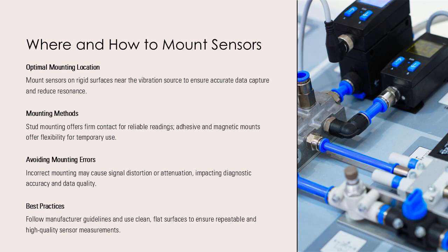Incorrect mounting can introduce errors like signal distortion or attenuation, leading to poor diagnostics. Therefore, following manufacturer guidelines and ensuring clean, flat surfaces are critical for repeatable and high-quality measurements.